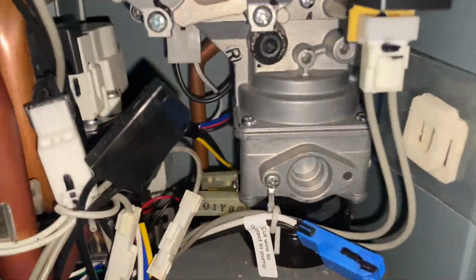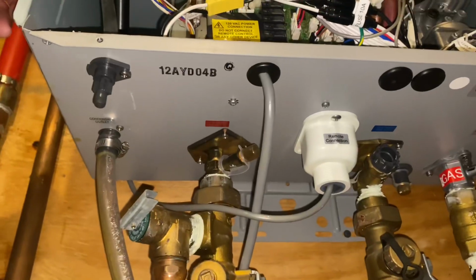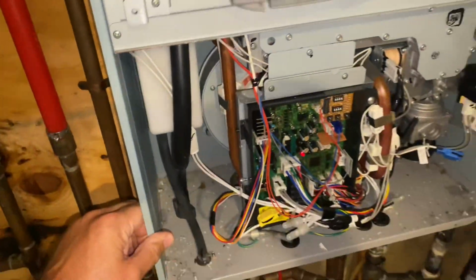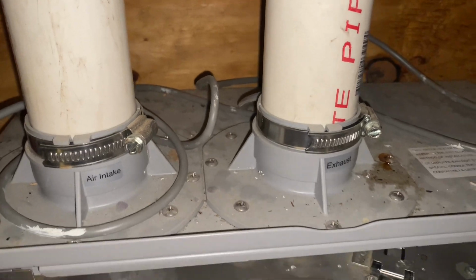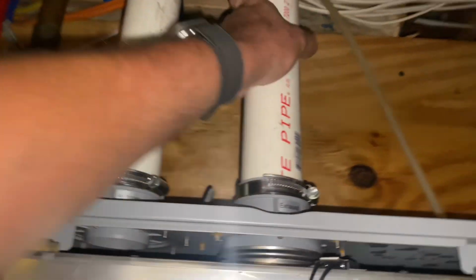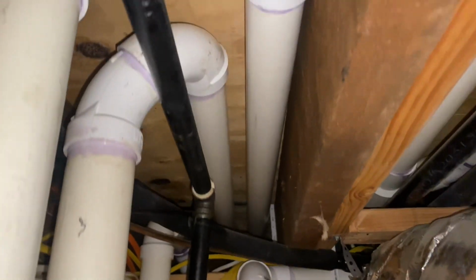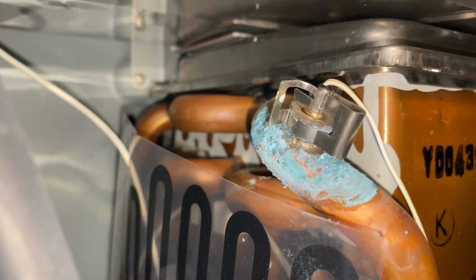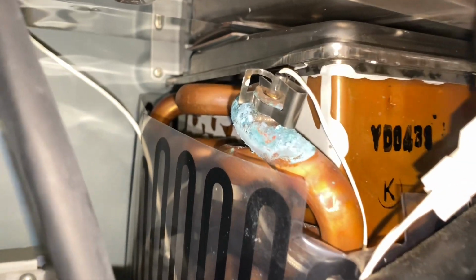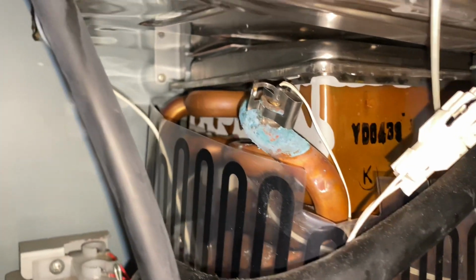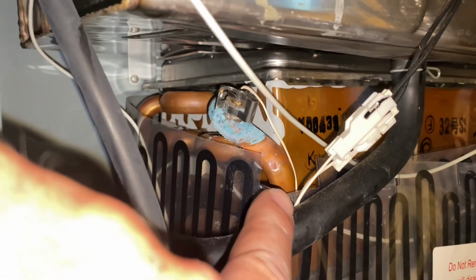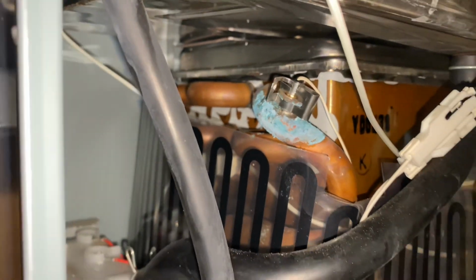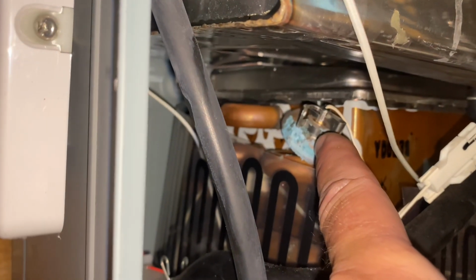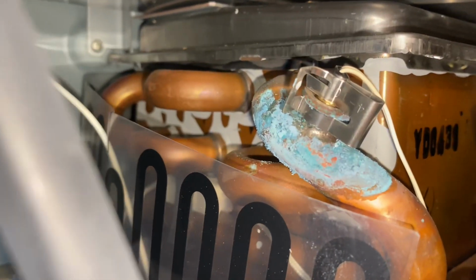Nothing else looks out of the ordinary here. I don't see any rust like you see on other manufacturers. Top is clean. There's your intake. Here's your exhaust. We'll check out our separation outside though. Make sure that's legit. All right, so we cycled the system about 12 times. I did notice this corrosion on the top left front corner of the heat exchanger. That green stuff, that's oxidation. You know, the Statue of Liberty is made of copper, and she's green or bluish green because water is there, and that is the heat exchanger outlet thermistor, and that's not good.